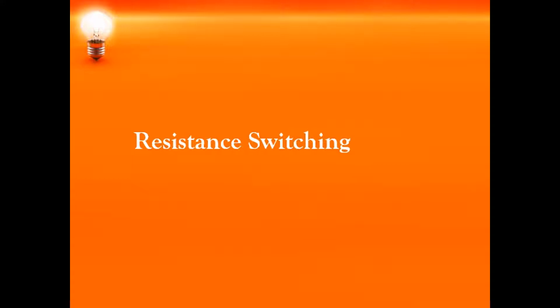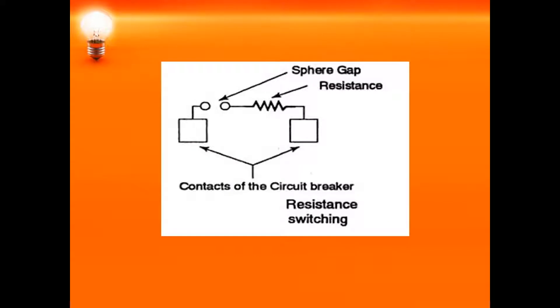Welcome to the session on resistance switching in circuit breakers. Whenever a fault occurs, the contacts of the circuit breaker get separated, and an arc is formed between them. This arc current is very high and has to be quenched using a suitable insulating medium, either a gas or a liquid. When the arc is quenched, a very high voltage appears across the circuit breaker contacts, which is known as the restriking voltage.